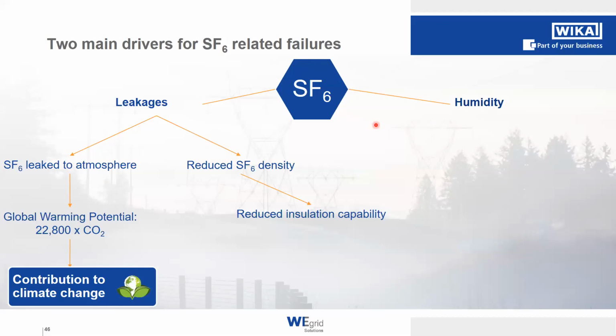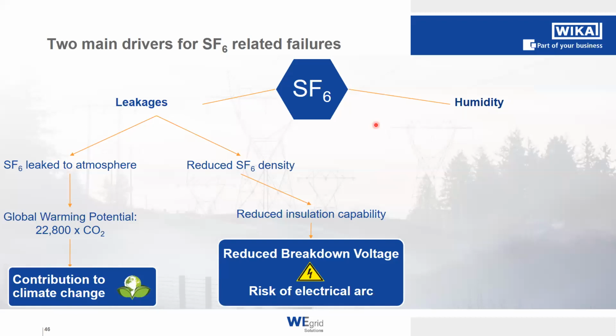On the other hand, if leakages occur in gas compartments, this reduces the SF6 density in the gas compartment, and less density means less insulation capability of the gas, and in return, a reduced breakdown voltage and a risk of an electrical arc, because the GIS does not function anymore in the way it was supposed to. So in the worst case, you have an electrical arc, or you have to shut off the GIS from the grid because it does not work properly anymore.